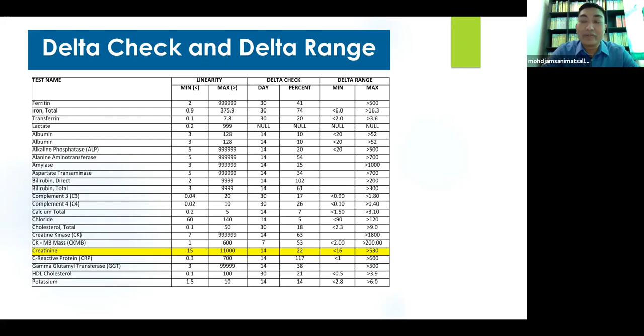So the delta check based on the RCV calculation for creatinine: our standard linearity of creatinine is 15 to 11,000 micromole per liter. And we choose the delta range of 16 to 530. Why do we choose 530? Because this is based on the medical decision limit, and we need a higher cutoff of the delta range, because our hospital is a nephrology center.